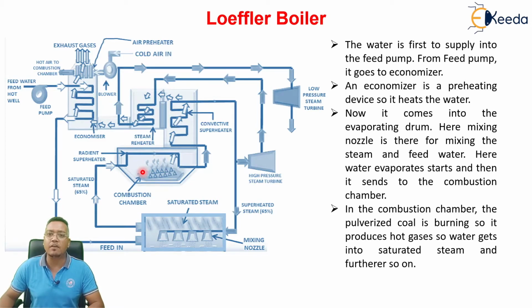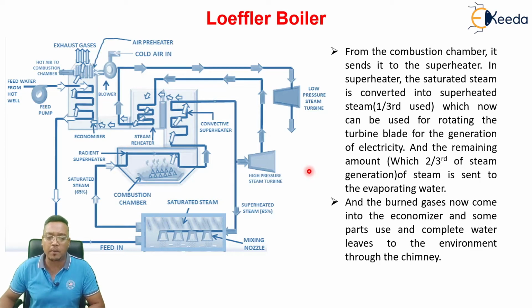Now let's see the flue gas path. This is the combustion chamber. The flue gas will be generated here and will pass through the radiant superheater, then the convective superheater, then the reheater, then the economizer, and it will go to the chimney. This is the path for the exhaust flue gases. Okay friends, now I have covered the working of the Loeffler boiler, and all the parts I have already covered.